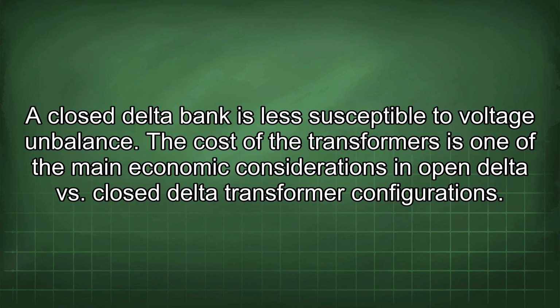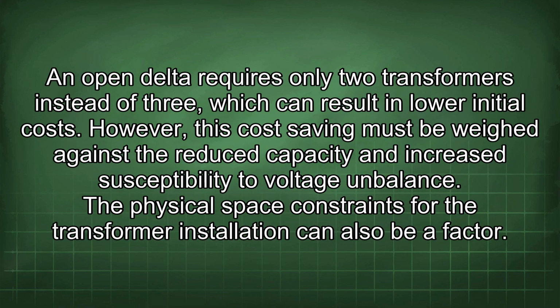A closed delta bank is less susceptible to voltage imbalance. The cost of the transformers is one of the main economic considerations in open delta vs closed delta transformer configurations. An open delta requires only 2 transformers instead of 3, which can result in lower initial costs. However, this cost saving must be weighed against the reduced capacity and increased susceptibility to voltage imbalance.